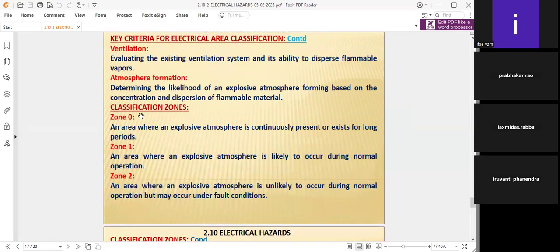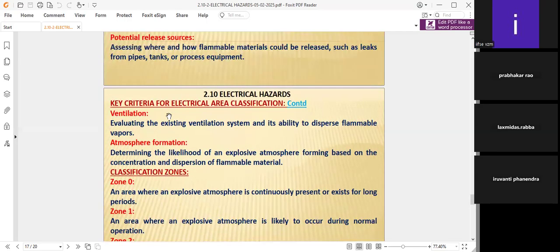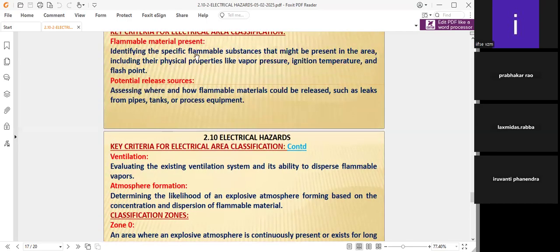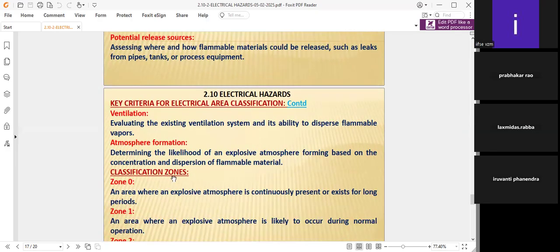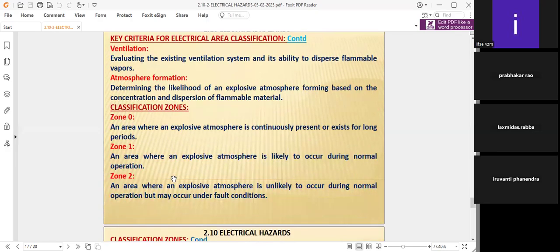The area classification of zones depends upon the risk: flammable materials, potential release of sources, ventilation, and the atmosphere. Keep these four things in mind to take care of the class 3 hazardous areas of industries, or we can say class 1 and class 2 also. Zone 0 is an area where an explosive atmosphere is continuously present or exists for long periods.